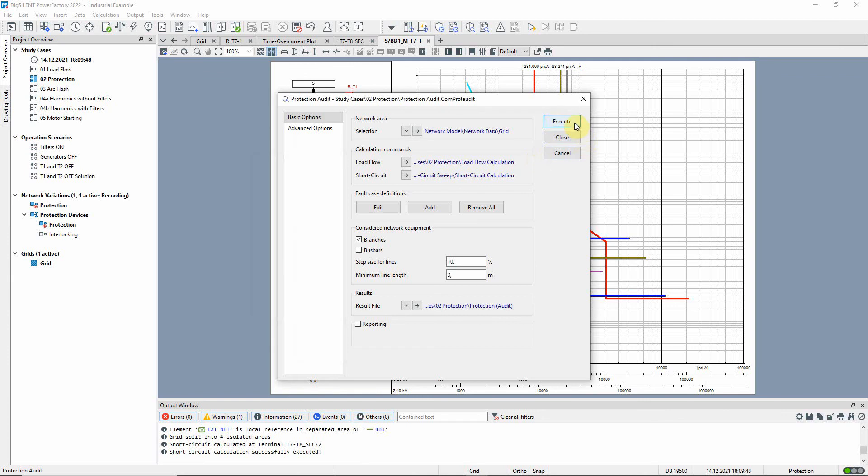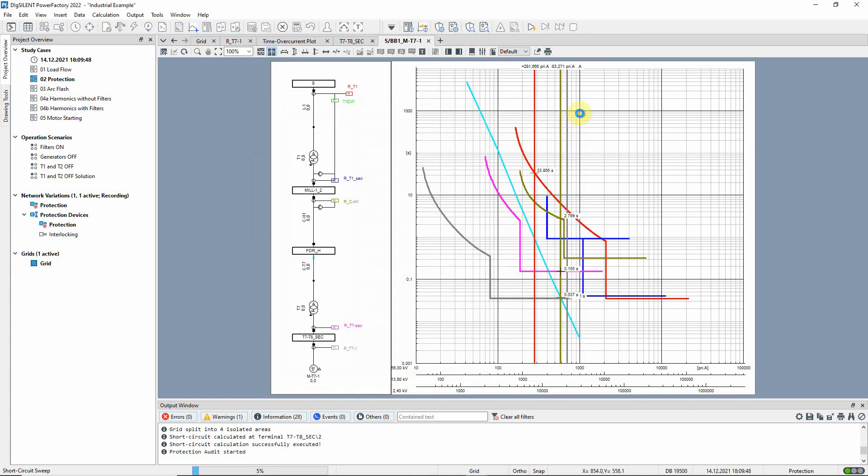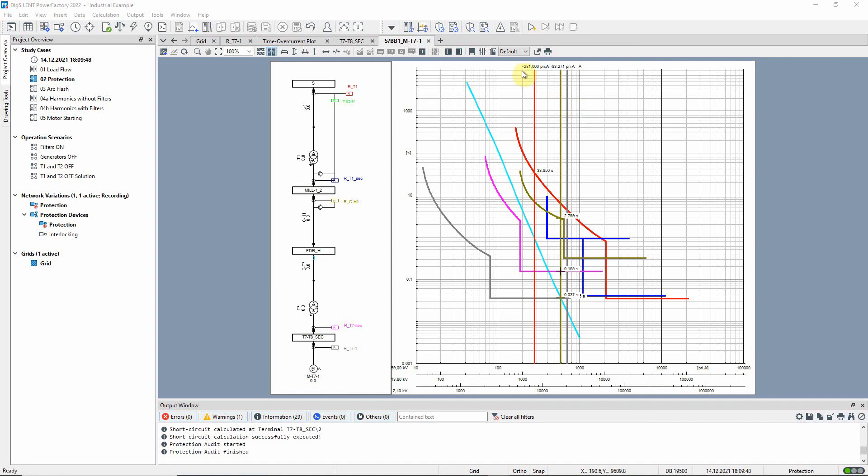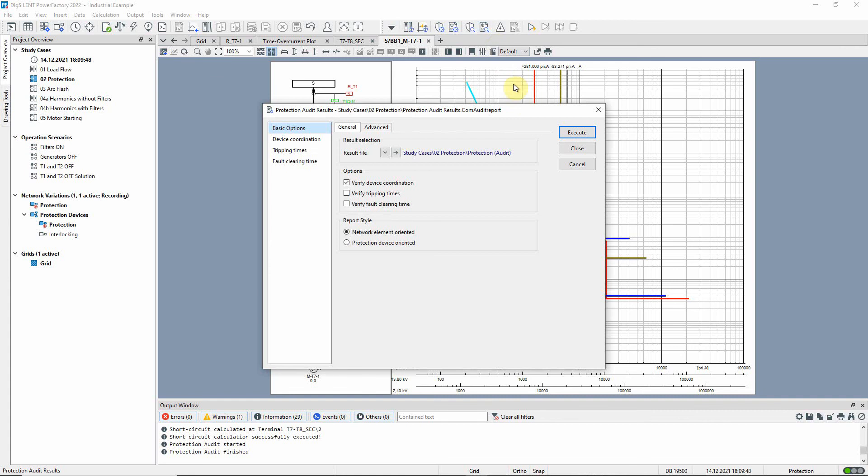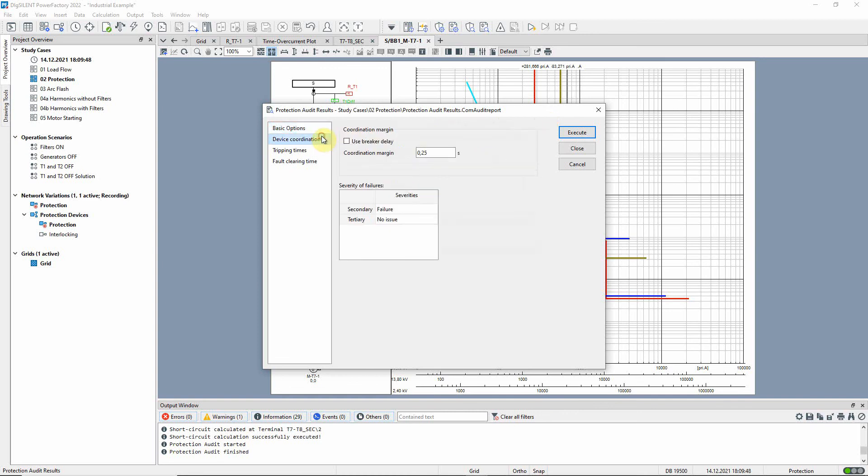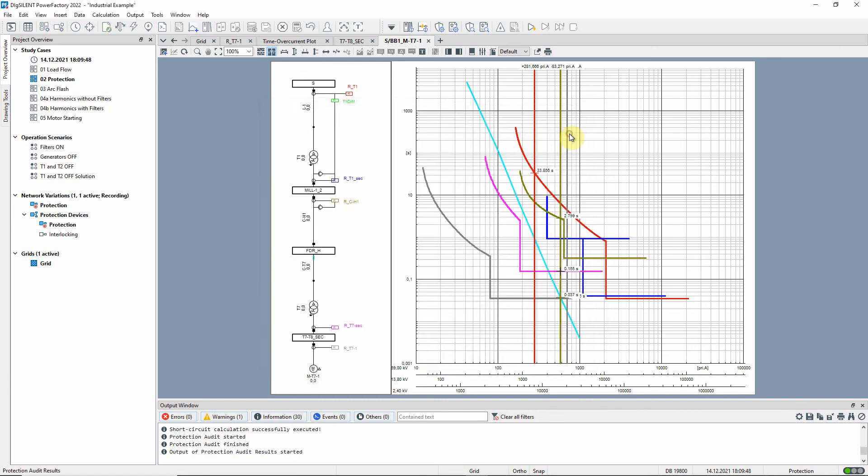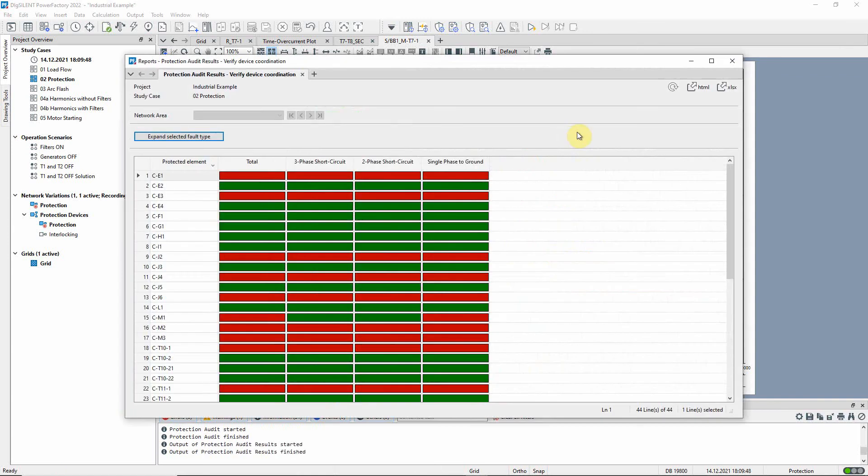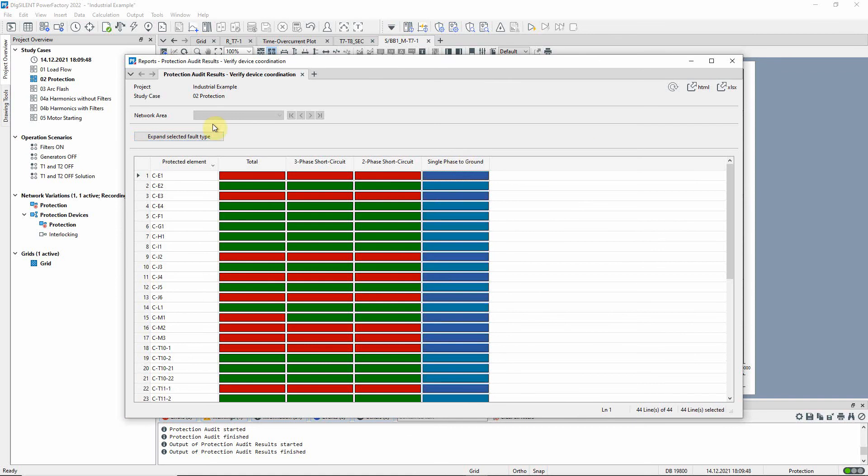The calculation is executed. Once the calculation is complete, the report can be run. We have selected verify device coordination which will compare the time delays between neighboring protection devices with the specified coordination margin. The report has a column for each short circuit fault type and these can be expanded separately.